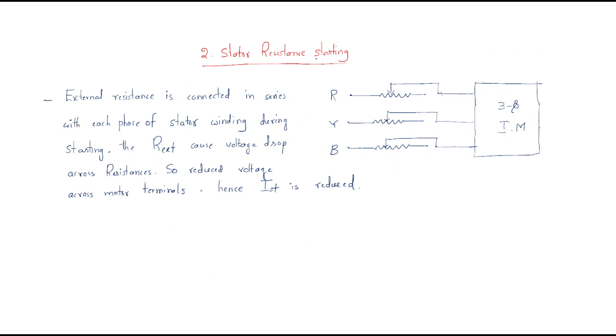The next method is stator resistance starting. In this method, we add external resistances before giving the three-phase supply to the stator. For the R, Y, B supply, three resistances are connected — external resistance is connected in series with each phase of the stator winding during starting. These resistances cause a voltage drop.